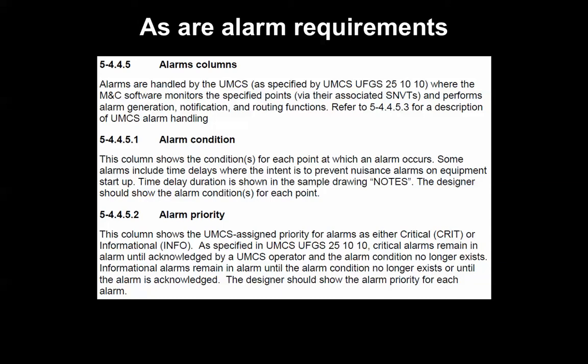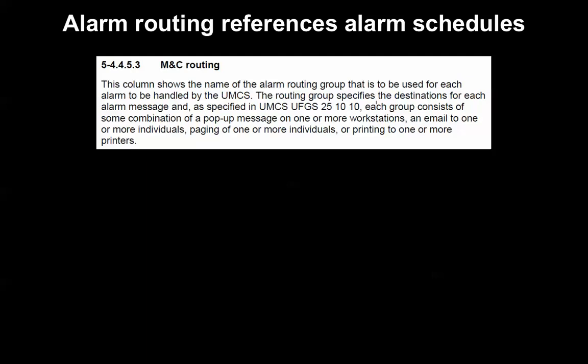And we also have alarm requirements annotated on this point schedule. Everything from what the condition is that triggers the alarm, what the priority is if it's critical or informational, as well as what routing groups that alarm goes to.